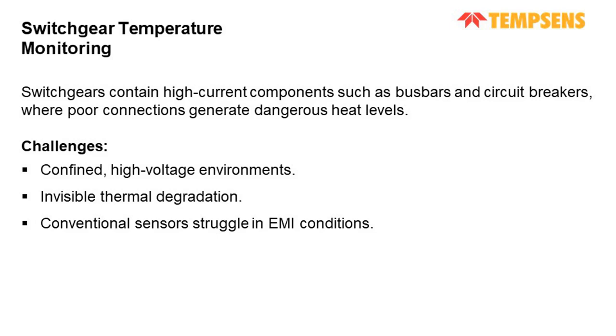So switchgears are essential for controlling, protecting, and isolating electrical equipment. However, the joints, terminations, and busbars inside can develop high resistance over time, leading to localized heating. And if left unchecked, this hotspot can cause insulation damage or even fires. But the challenge lies in monitoring temperature inside a confined high voltage cabinet where conventional sensors can't operate safely due to the electromagnetic noise and presence of high voltages.